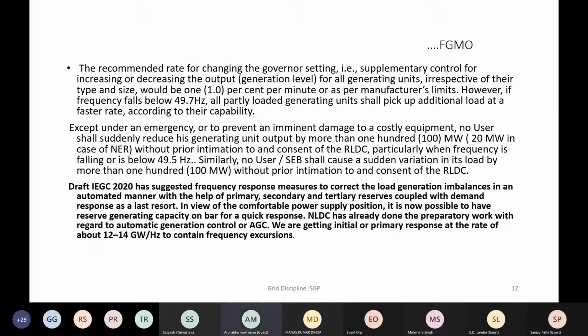Sir, theoretically it is proved that AGC does not have any effect on the billing of the generations. But practically it is not possible, because those people who are working in the control room are always watching the frequency and always put the machines in RGMO. So if for the secondary response you have to maintain the frequency response through the AGC, it's not possible to back down the generations. And if we back down the generations, then a highly negative UI will be reflected in our UI schedule. So I think, sir, the matter is still not clear.